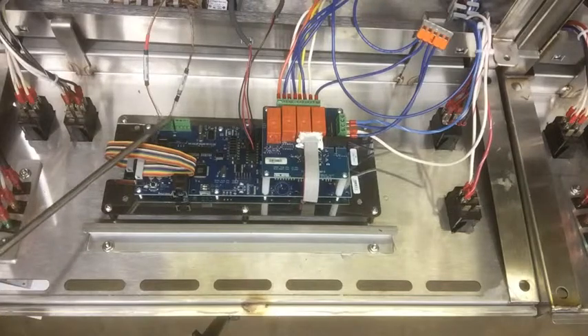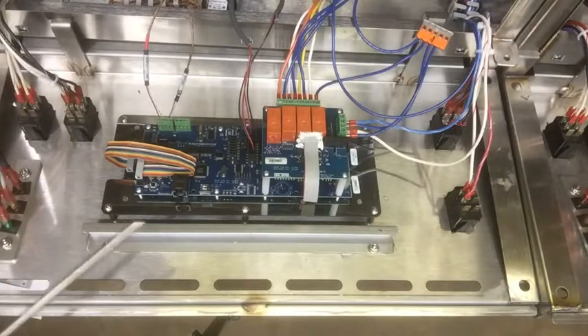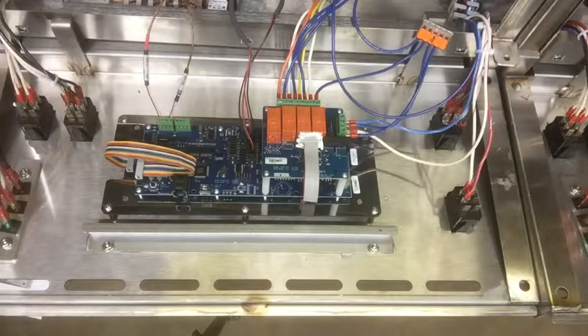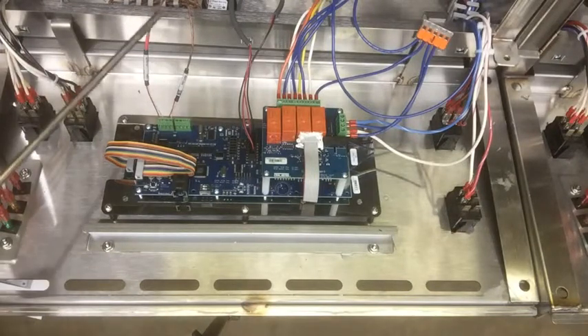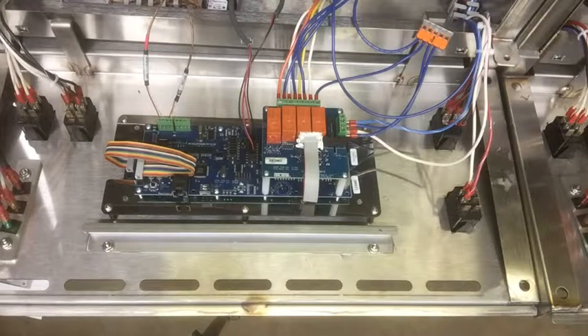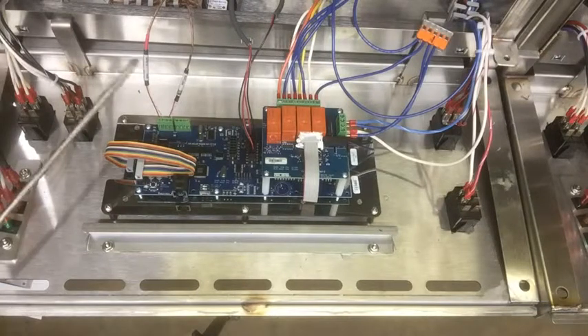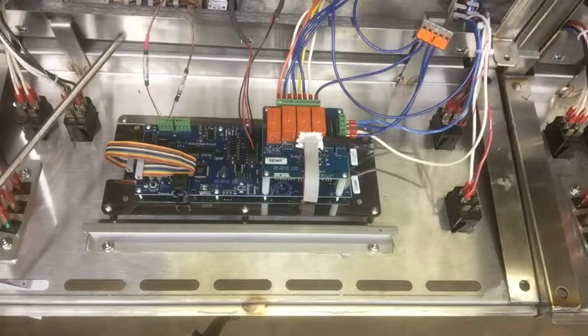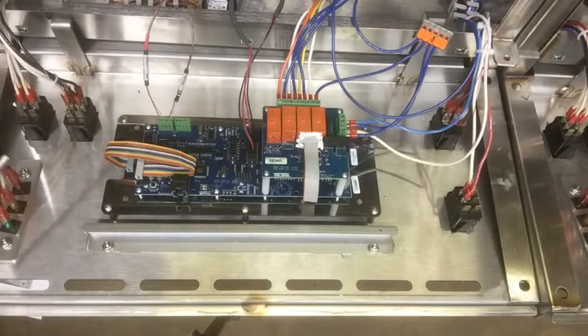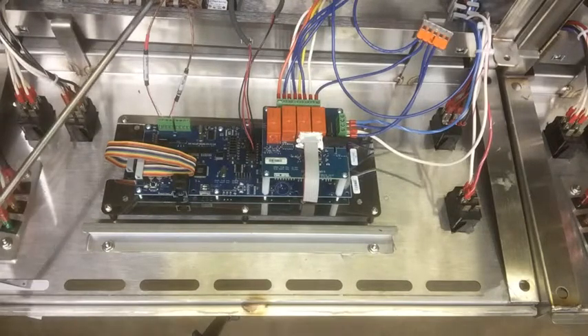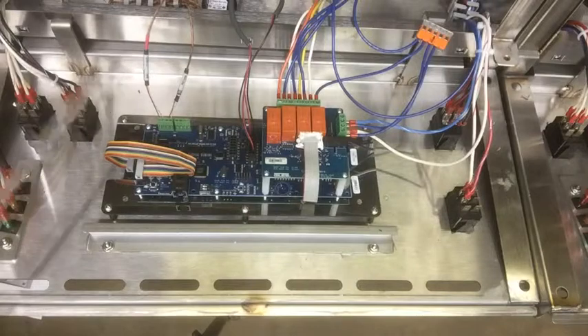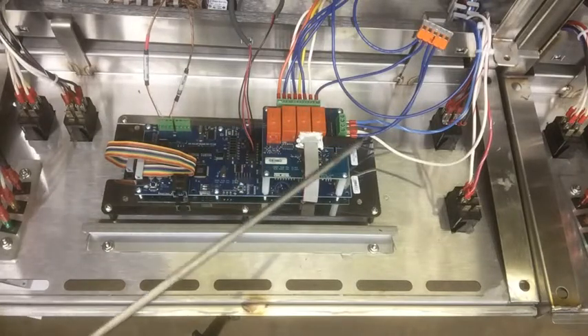This probe right here is your variable probe. It is the probe that the controller looks at to control the temperature of the oil. This is your element probe coming in here. It is the one that's tied directly to the element, and it senses too hot an element. If there is no oil on the element, it is going to get to an excessive temperature. We set that up in our max element temperature settings inside the controller, and during programming we'll talk about that. But when it exceeds that temperature, this is where that is.